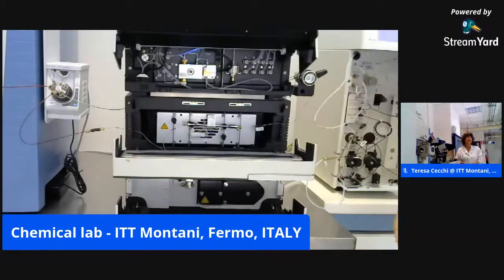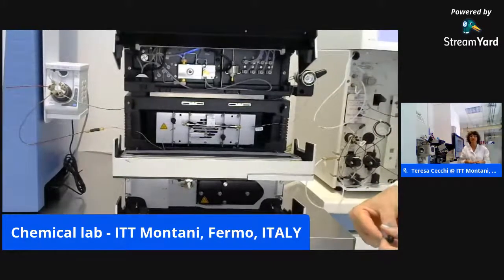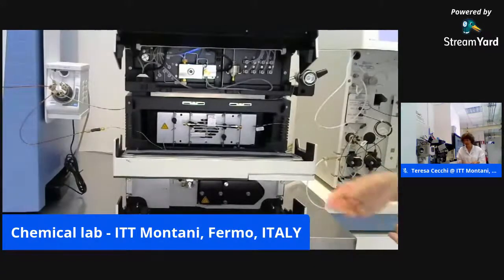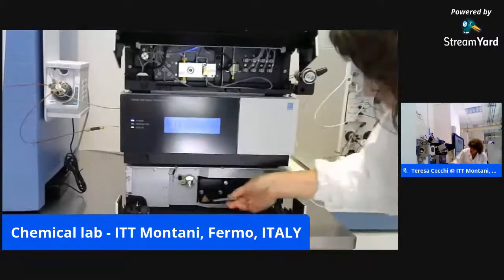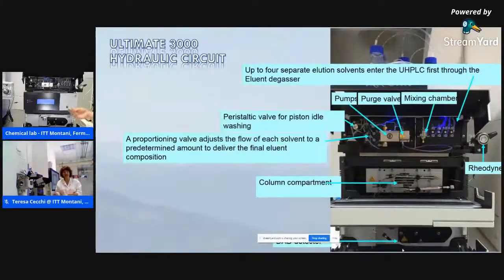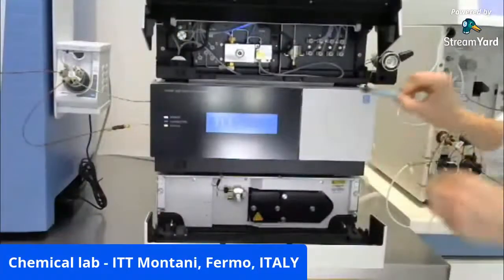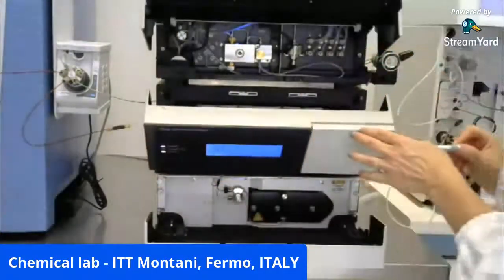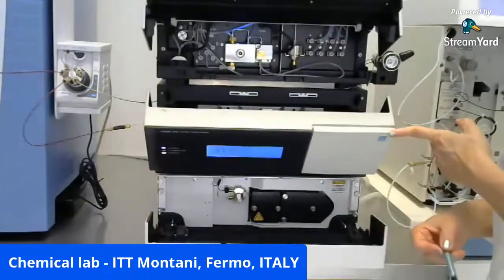So you will probably understand that this is very important in the pharmaceutical sector, where we have a very wide range of polarity for our analytes. And from the column, we go into a diode array detector that is here. The detector is a diode array because we need a very fast wavelength scan. We cannot use a sequential wavelength scan, but we have to get all the wavelengths acquired and detected simultaneously to prevent analytes that were previously separated in the column from getting mixed again in the cell here. So I need a very, very fast detection.